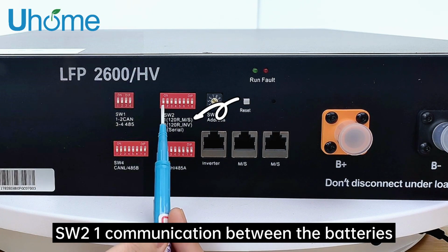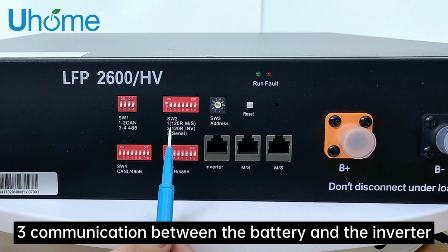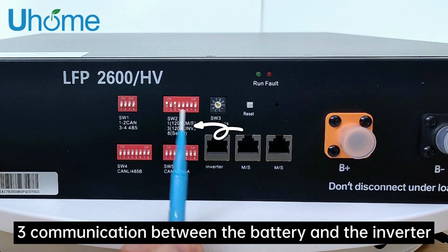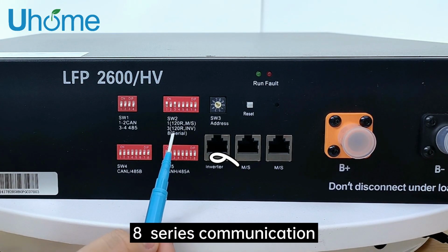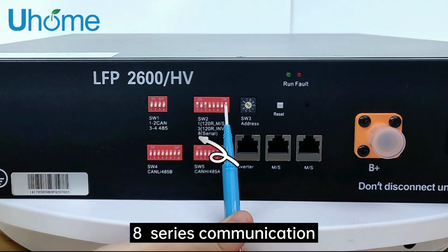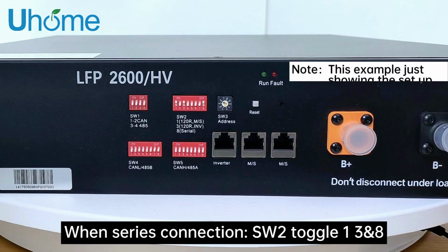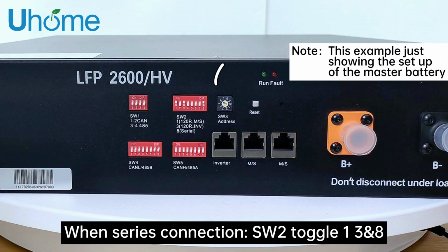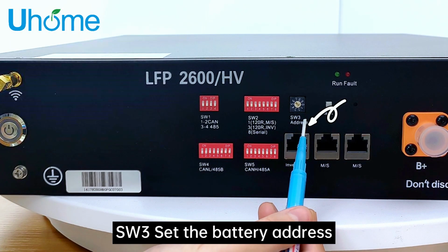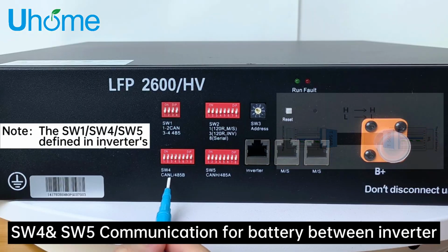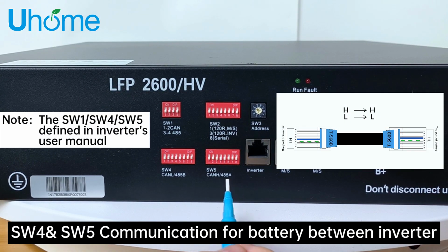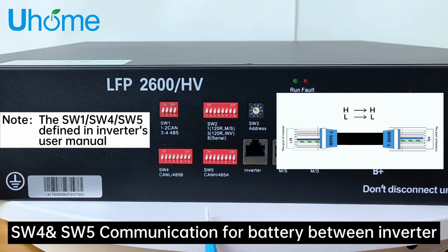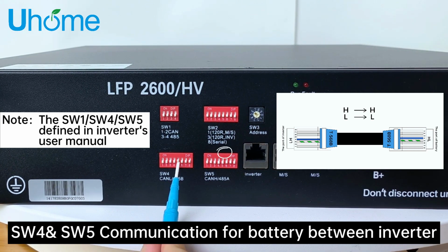SW2 1: communication between the batteries. 3: communication between the battery and the inverter. 8: series communication. When connected in series, toggle SW2 switches 1, 3 and 8. SW3 sets the battery address. SW4 and SW5: communication for the battery with the inverter.